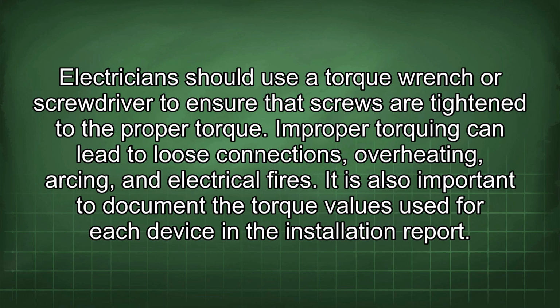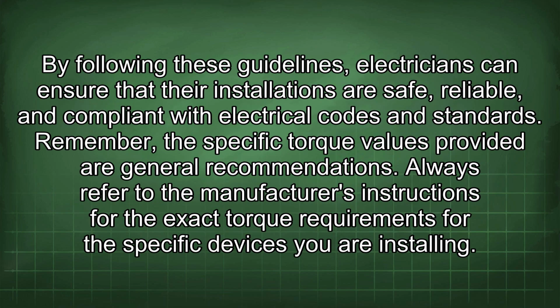Electricians should use a torque wrench or screwdriver to ensure that screws are tightened to the proper torque. Improper torquing can lead to loose connections, overheating, arcing, and electrical fires. It is also important to document the torque values used for each device in the installation report. By following these guidelines, electricians can ensure that their installations are safe, reliable, and compliant with electrical codes and standards.